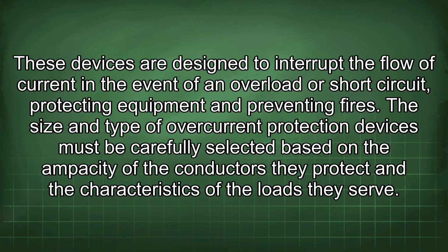These devices are designed to interrupt the flow of current in the event of an overload or short circuit, protecting equipment and preventing fires. The size and type of overcurrent protection devices must be carefully selected based on the ampacity of the conductors they protect and the characteristics of the loads they serve.